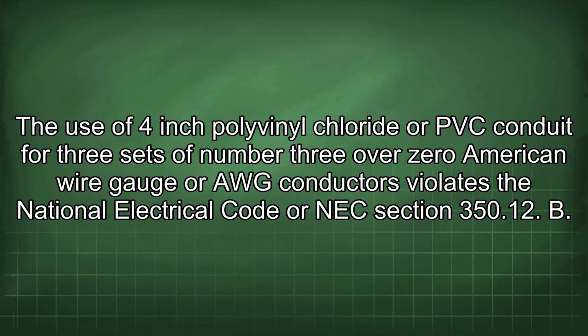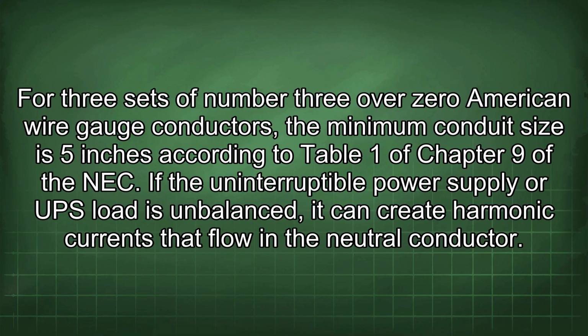The use of 4-inch polyvinyl chloride or PVC conduit for 3 sets of number 3/0 American wire gauge or AWG conductors violates the National Electrical Code or NEC section 350.12.b. For 3 sets of number 3/0 American wire gauge conductors, the minimum conduit size is 5 inches according to Table 1 of Chapter 9 of the NEC.